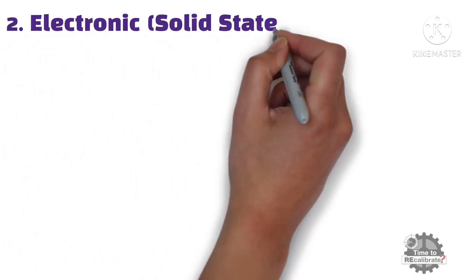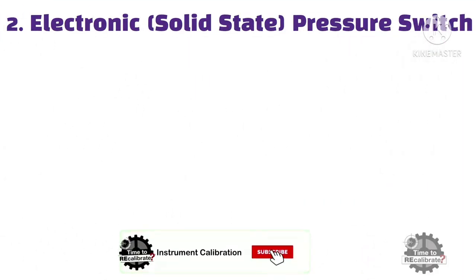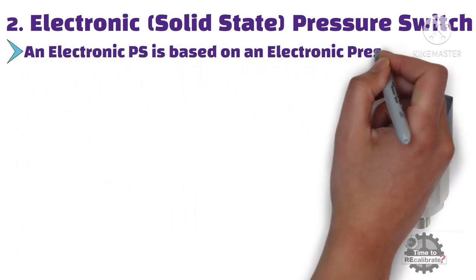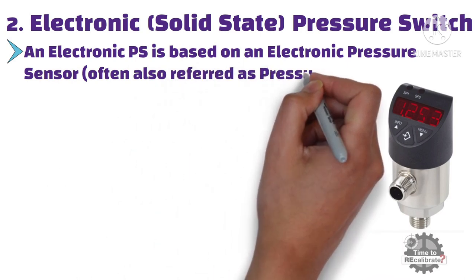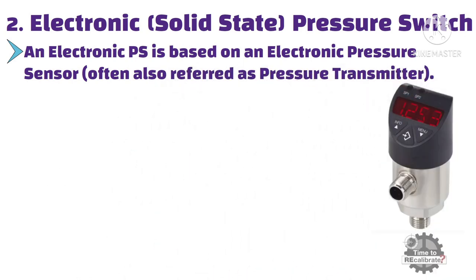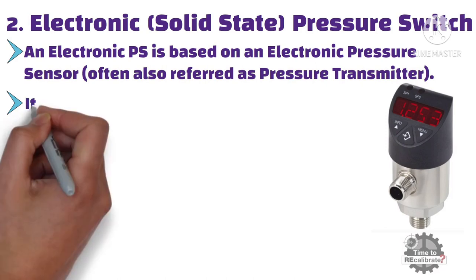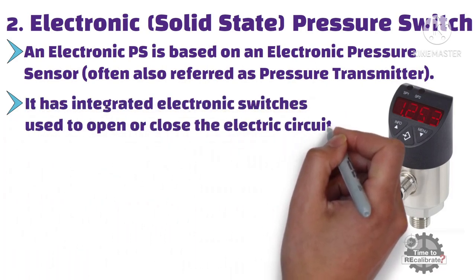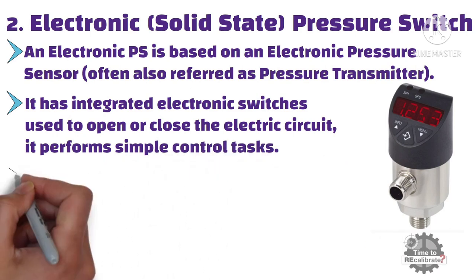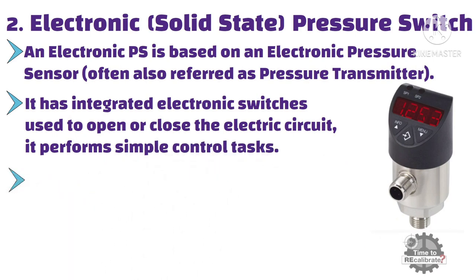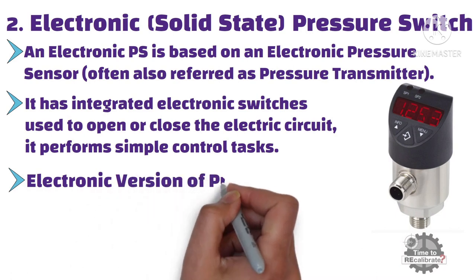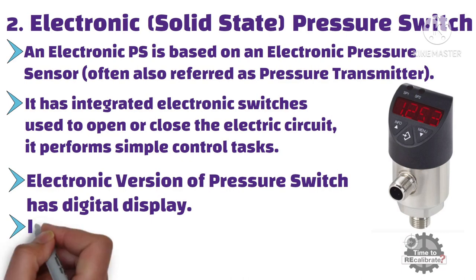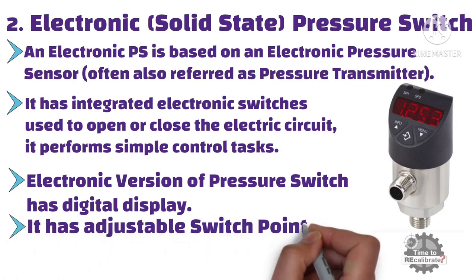Secondly, what is an electronic or solid state pressure switch? An electronic pressure switch is based on an electronic pressure sensor, and it is often referred to as a pressure transmitter. It uses integrated electronic switches to open or close the electric circuit and performs simple control tasks. As you can see from the picture, the electronic version has a digital display, adjustable switch points, and considerably higher reliability.